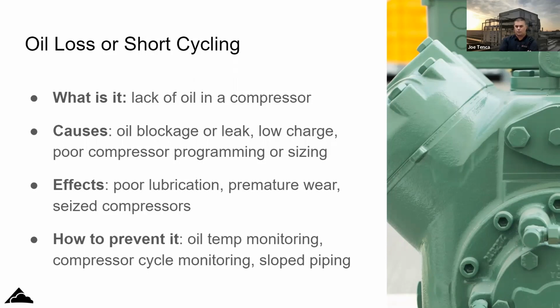That was a common thing for a long time, those oil valves plugging up and getting dirty, especially under high load. They could feed enough when the load was low, but if it got really high, the little oil valve, I forget the model number, just wouldn't feed enough oil. So you have to pull it apart and clean it. And as soon as you clean it, you got your flow rate back to fill all your compressors up. I think that's another perfect example of, hey, I wasn't on site to see it, so pulling out my gauges or looking at sight glasses just doesn't help. What I really need to do as a technician is look at historical data to see what happened the last time there was an oil trip, for example, and try to diagnose using that. Am I getting that right, Joe?